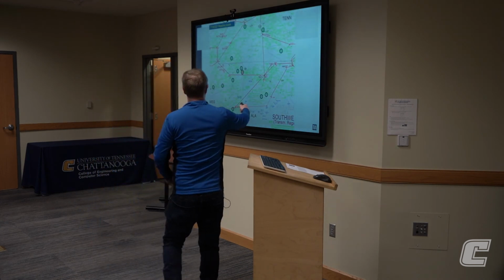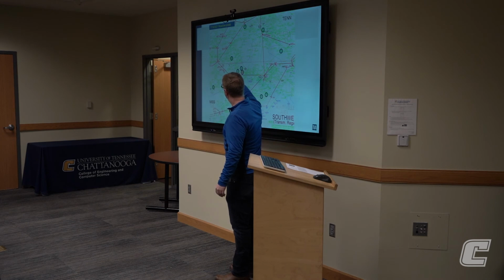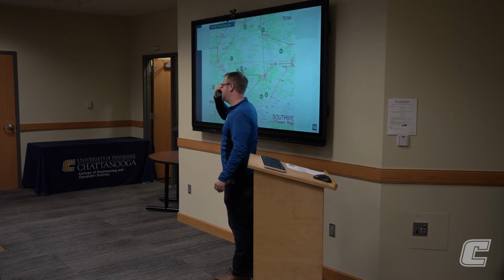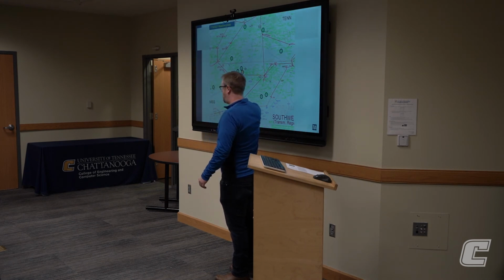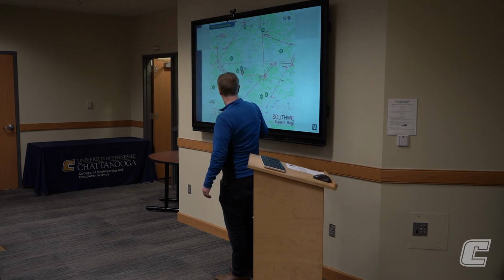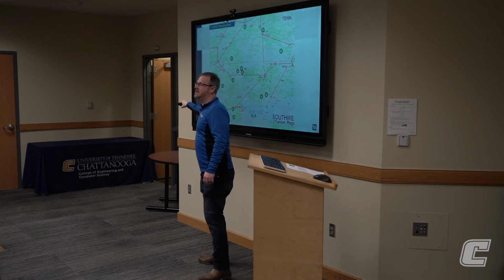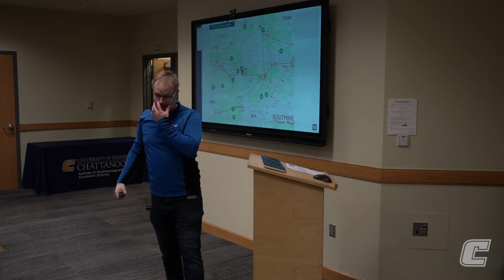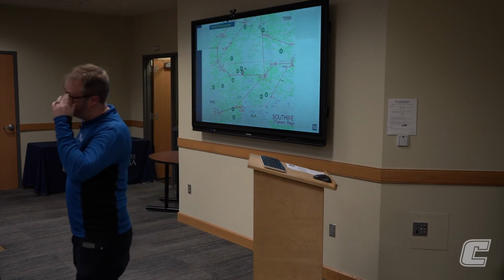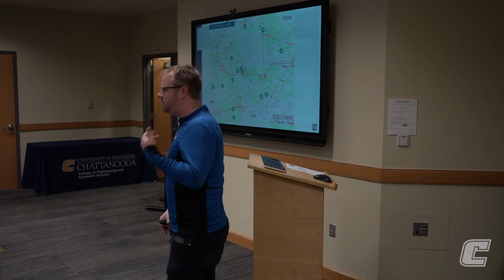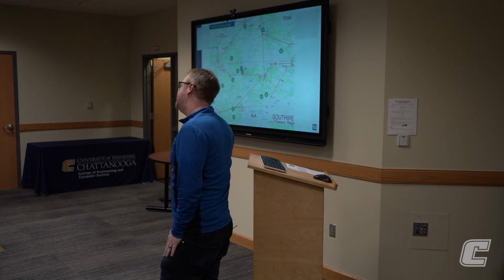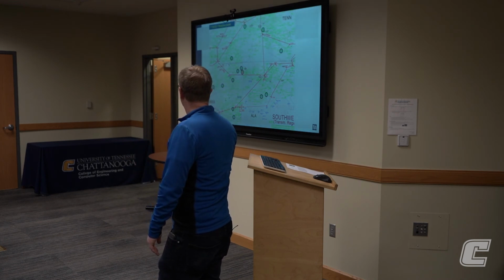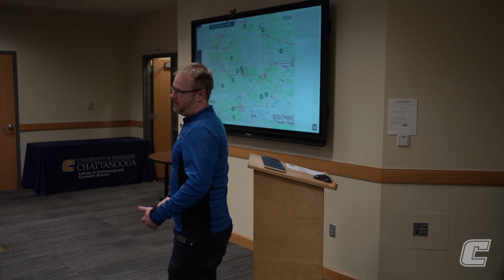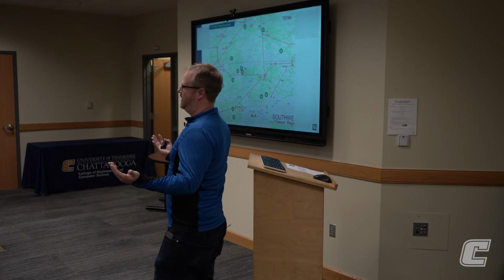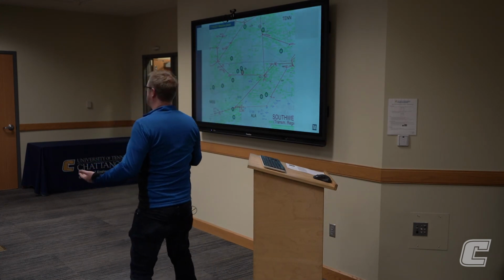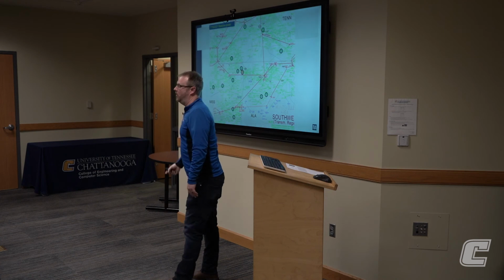What's crazy is shown on this map, that solar plant is right here. We had customers complaining about these oscillations. Everywhere there's a dot, we could see it with other instrumentation. Now, we didn't lose any customers, but they could see it, like, what's going on, my voltage seems erratic. So that's why you have to be careful. If you tie even a solar plant to the grid, you can cause problems in a large area.